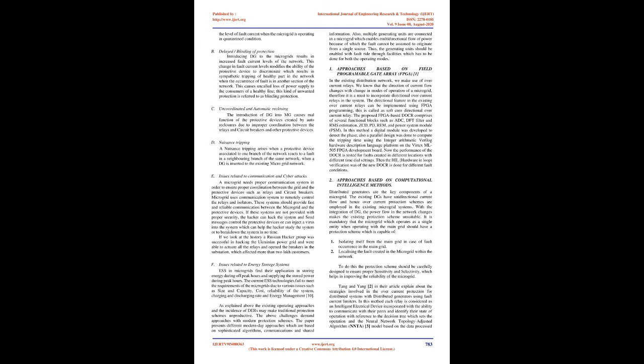As explained above, the existing operating approaches and the incidence of DERs may make traditional protection schemes unproductive. The above challenges demand approaches with modern protection schemes. The paper presents different modern-day approaches which are based on sophisticated algorithms, communications, and shared information. Also, multiple generating units are connected in a microgrid, which enables multi-directional flow of power, because of which the fault cannot be assumed to originate from a single source.